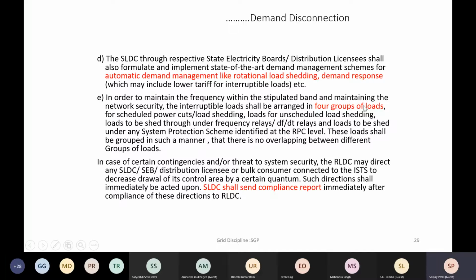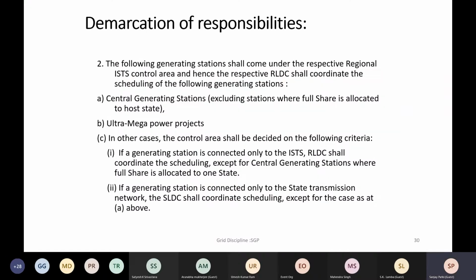And as I said, there are four groups of load set to be tripped based on the under frequency and df/dt, the under frequency relays and df/dt relays. We saw those proposed settings of the frequency at the 2020 amendment recommendations of the grid code.